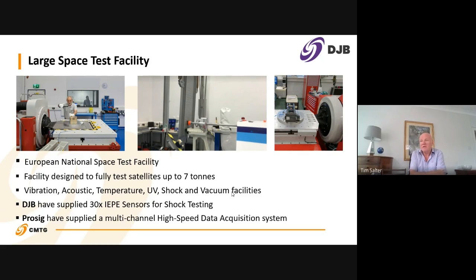We supplied about 30 IEPE sensors for this, for shock testing. And our sister company, Prosig, also supplied a multi-channel data acquisition system. So the middle photograph actually shows their shock test machine. So a satellite component or a small satellite is bolted on this face of the plate. And then we have a pneumatic ram system where this ram is fired at the back of the plate. And just here, where you can see this red mark, in order to modify the shock pulse to make it a very sharp rise time or less, they would put a material between here, which can be some sort of plastic, aluminium, or even steel if they want a really sharp rise time.